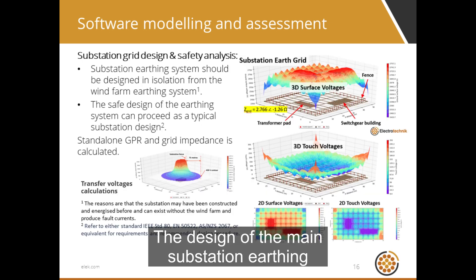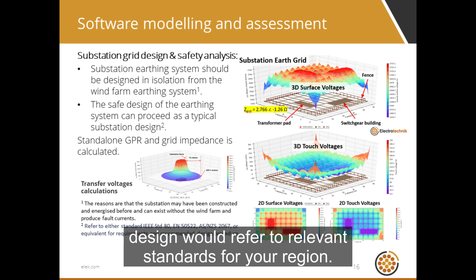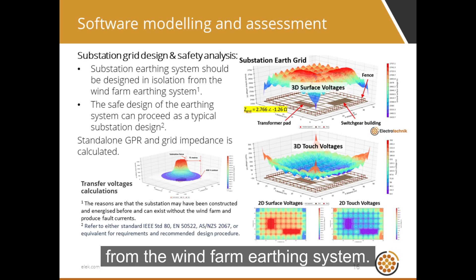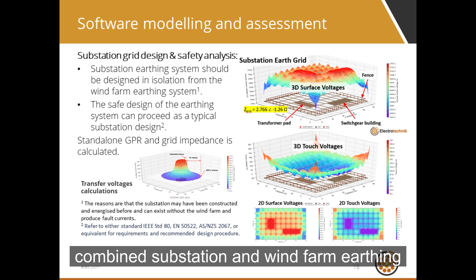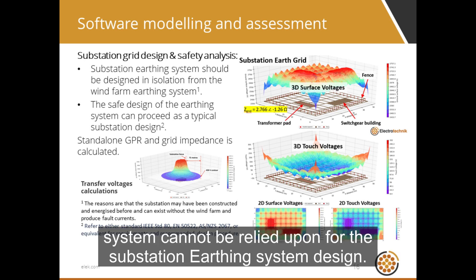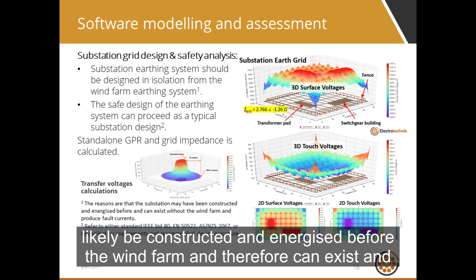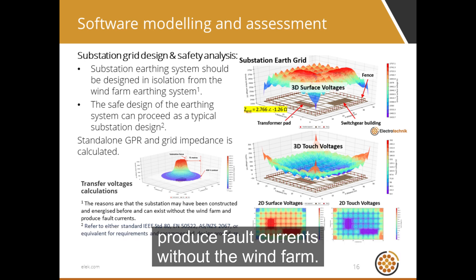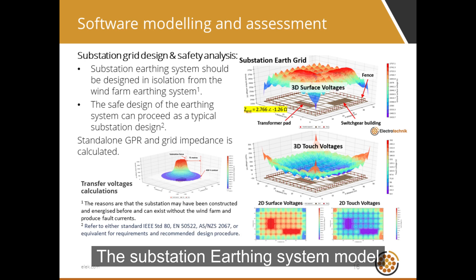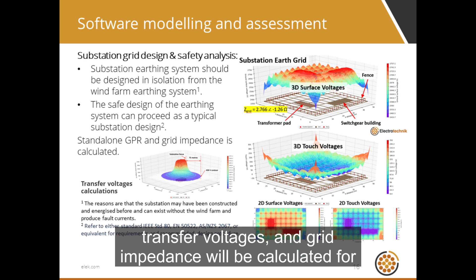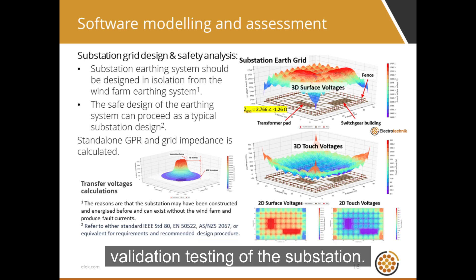The design of the main substation earthing system can proceed as a typical substation design would. Refer to relevant standards for your region for the substation earthing requirements. The substation earthing system should be designed in isolation from the wind farm earthing system — the benefit of the combined system cannot be relied upon, because the substation will most likely be constructed and energized before the wind farm and can produce fault currents without it. The substation earthing system model includes the meshes, steel reinforcement from the concrete slabs, and the fence. The stand-alone ground potential rise, transfer voltages, and grid impedance will be calculated for validation testing of the substation.